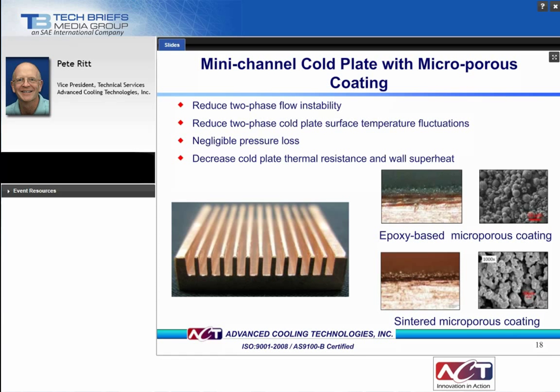ACT has developed a technology to reduce two-phase instabilities by creating a surface coating that improves nucleation. The coating creates a porous surface that promotes the formation of nucleation sites and reduces the superheat required to boil. The result is a more stable evaporation process.